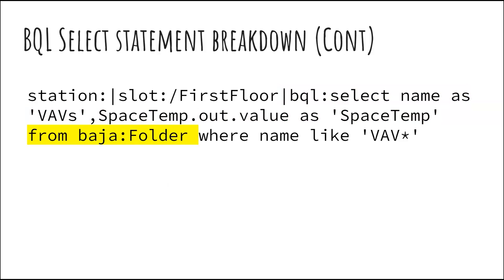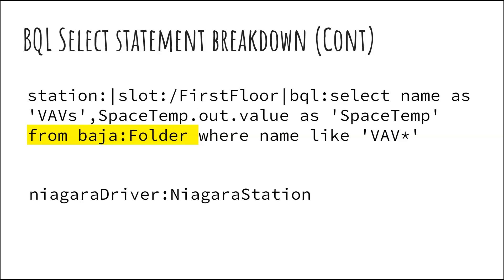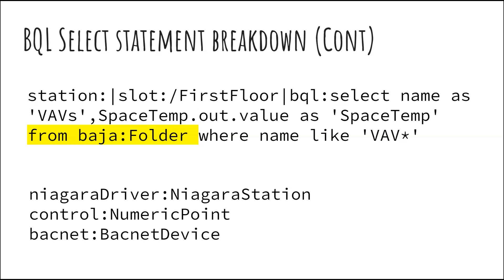Then we have what we call the predicate — this is really the first half of our predicate, where we start to filter down to the results we want. In this case, I'm using 'from Baja folder,' which tells it to ignore all components that aren't of type Baja folder. The same can be done for nearly any other type, such as niagaraDriver:NiagaraStation, station, control:NumericPoint, and bacnet:BACnetDevice.